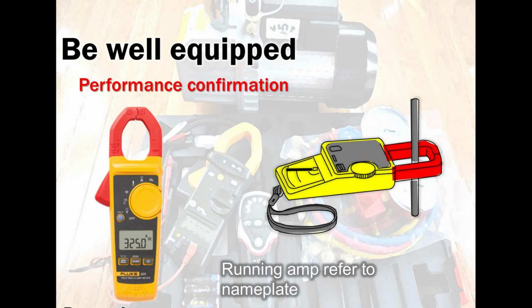And if you cannot find the correct running amps, put the unit in test run. I will explain to you in the next slides how to put the unit into test run. It's very simple. In test run, the compressor is going to run at a fixed frequency. And that's the time you can measure the true running amps, total running amps, total pressure.